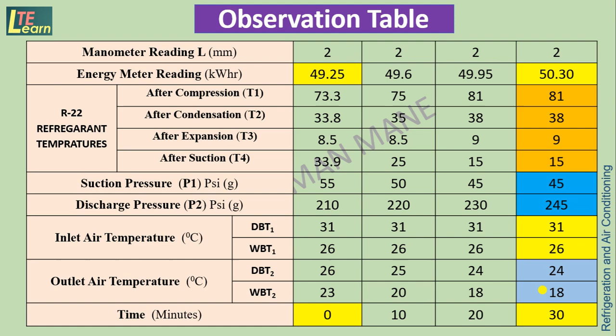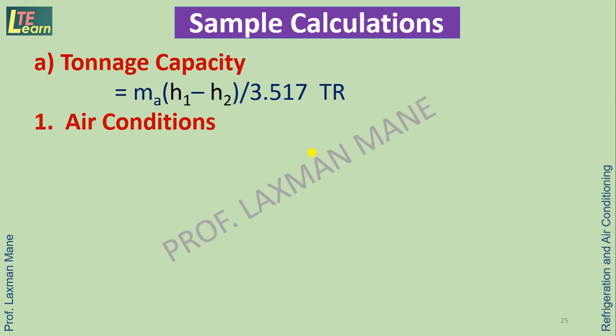Now by using these readings we can have a sample calculation. First we calculate tonnage capacity. The formula for it is mass flow rate times the enthalpy difference between inlet and outlet of the air. H1 is enthalpy at inlet of duct and H2 is enthalpy at outlet of duct. 3.517 is the conversion factor from kilowatt to TR, means ton of refrigeration. Air conditioning in that condition of air which are taken.